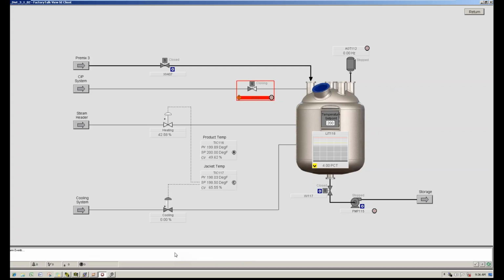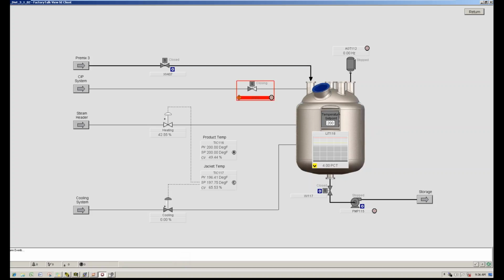That's because I haven't yet configured the alarms for the system, and I'm going to show you the Alarm Builder tool and how that can quickly generate the alarms and bring them into the FactoryTalk View environment. So at this point in time, I've configured the system, I've built it, I've been through my basic pre-commissioning, I've proven all my I/O, I've gone through and I've enabled the alarms that I want to use, and then I can turn to my Alarm Builder tool to generate the alarms.